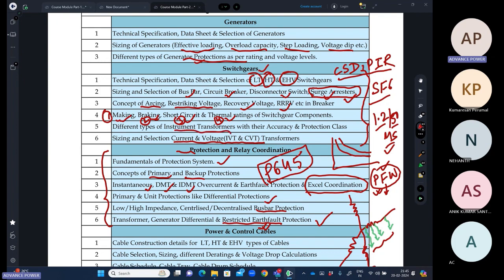For instrumentation transformers, we will discuss the accuracy and protection class. For CT, you have metering classes like 0.1, 0.2, 0.2s, 0.5, 0.5s also. So what are the differences? Where you are using which type of CTs as per the accuracy: for protection, for normal metering, for tariff metering. What the differences are and what accuracies we are measuring is very important. So we'll discuss from LT CTPT to CTPT, which are being used in the EHV system, in much detail.